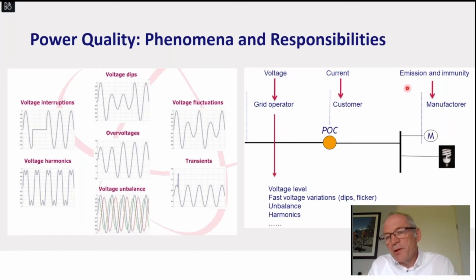There's also the responsibility of the manufacturer, who is responsible for his device or equipment, that it is not injecting too much inrush current, harmonic current, or super harmonics into the network, but also has some immunity against voltage distortions. So there's always an interaction between the current of the installation and the voltage of the network operator, depending also on the impedance of the network.